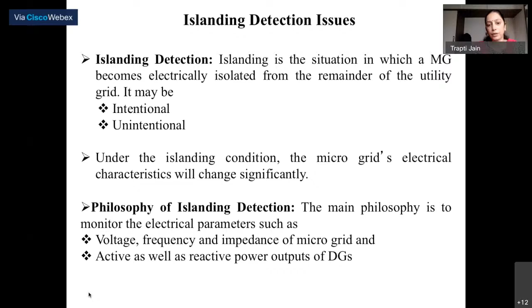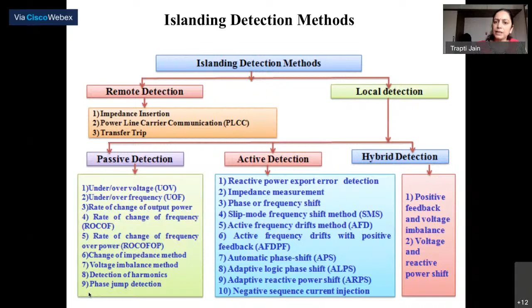By monitoring this, we can detect islanding. There are several techniques, such as remote detection and local detection. Remote detection utilizes communication infrastructure to detect islanding, while local detection monitors voltage, frequency, and impedance, and based on that decides whether islanding has happened.